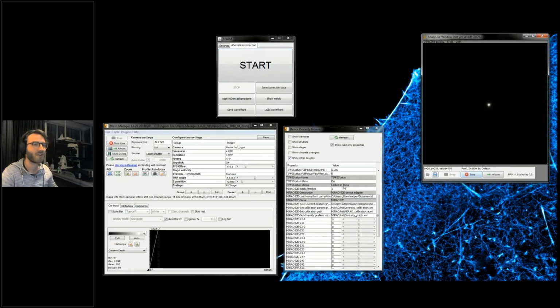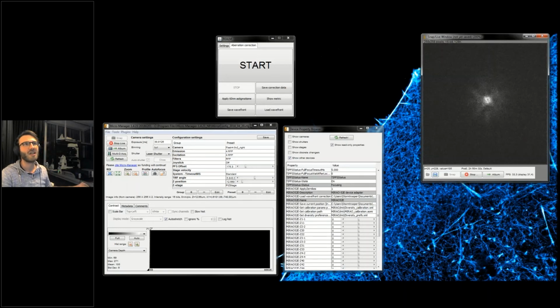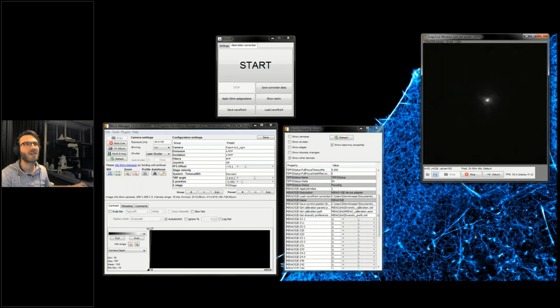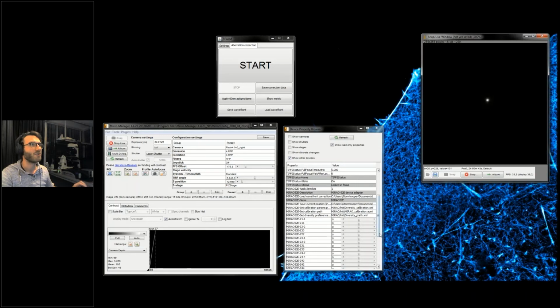Currently I have a sample mounted in the microscope with beads and Alexa 647 coated to the coverslip. It's not very interesting for a reconstruction, but it's a very nice demonstration of the use of the plugin. As you can see, this is our bead, and I can go through focus. It looks reasonable, but not perfect. This might be, for instance, some drift in the system. So we can start by just using the plugin to correct or flatten the deformable mirror.